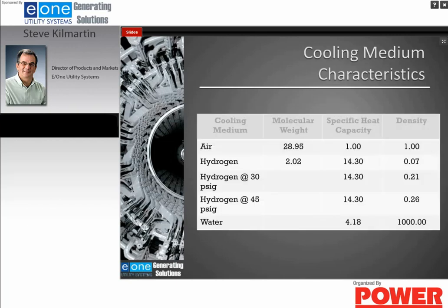This chart gives you an idea of the differences in the specific heat capacity of hydrogen versus air. You can see when hydrogen is at 45 psig, it has about 14 times the specific heat capacity of air. And also note the density on the far right: when hydrogen is pressurized at about 45 psig, it is 4 times less dense than air.